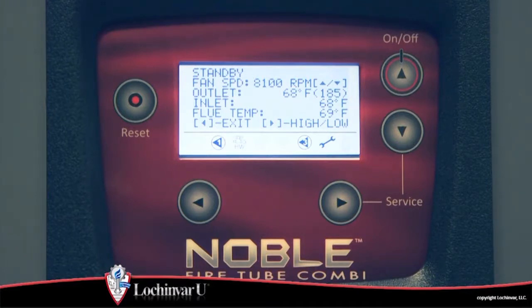The unit will fire at its normal ignition speed and will then modulate its firing rate to 100%. During service mode, the control will ignore all other heat demands.